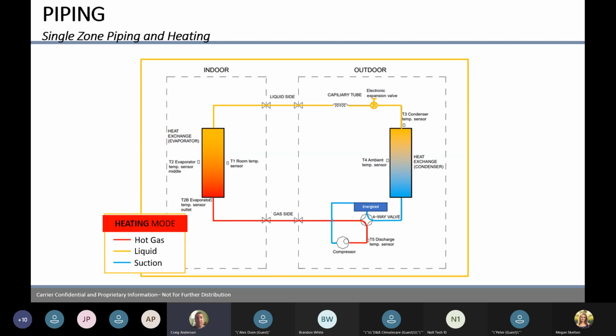And then you notice in the heating mode, now our reversing valve is energized. So our flow of gas has changed. Now we're into our heating mode. That's all that is doing, is changing the flow of gas.